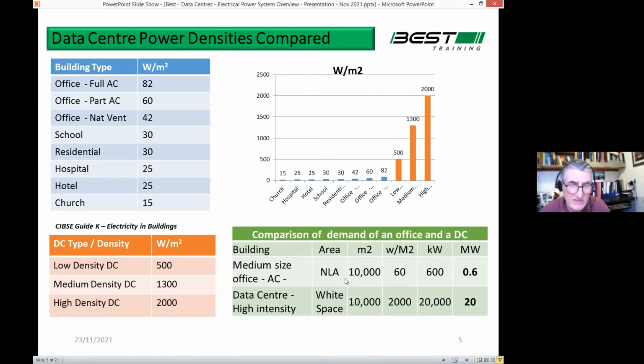So 10,000 square meters will be a medium-sized office, like one of the offices you see along the north wall there, a banking headquarters, that type of thing. 10,000 square meters at 60 watts per square meter gives you 600 kilowatts, or 0.6 megawatts to get the language right. So we're talking megawatts, right? 0.6. The same floor print for a high intensity data center is 20 megawatts. And that's typically what we're talking about with data centers, 20 megawatts.